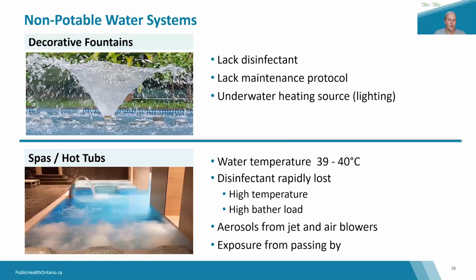So spas and hot tubs have also been associated with cases. The water temperature of spas or hot tubs is warm and ideal for Legionella growth. While operation of public spas is regulated in Ontario and disinfection is required, the disinfectant is rapidly lost because of the high water temperatures and the high bather load relative to the amount of water. Spas and hot tubs are often equipped with jets and air blowers, which can generate aerosols. And those that are using the spa are most at risk, but those who are passing by can also be exposed to aerosols. So proper maintenance and compliance with Ontario regulations will help reduce the risk.